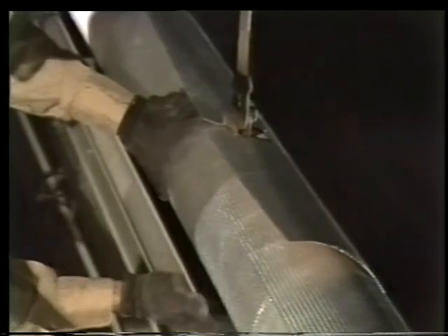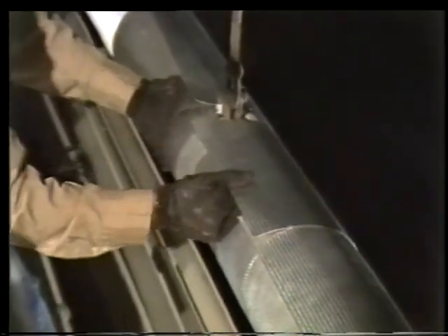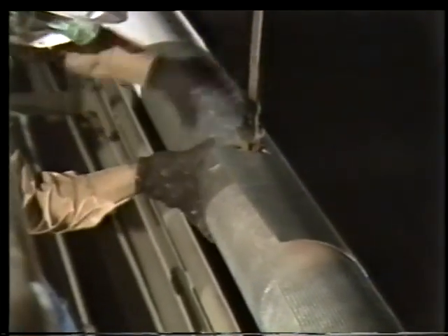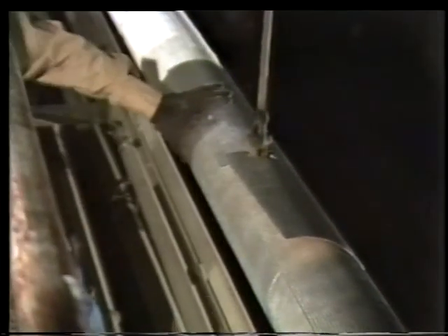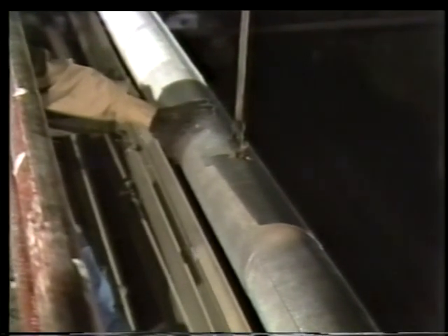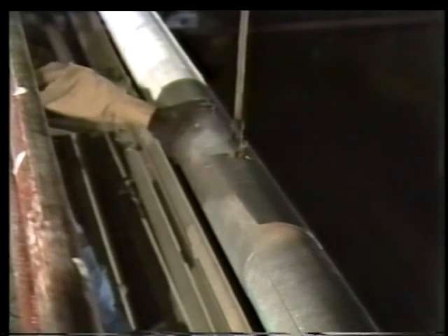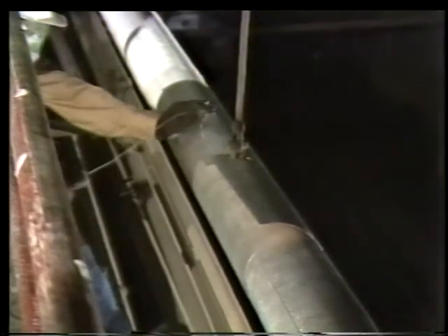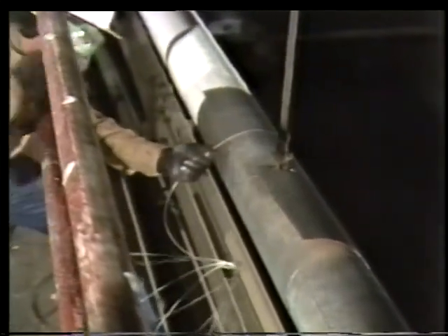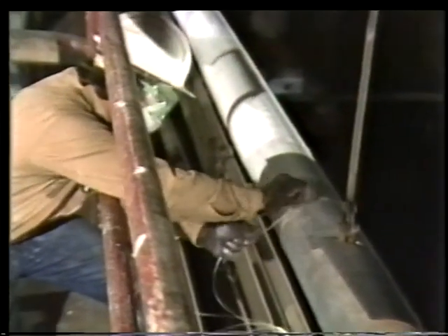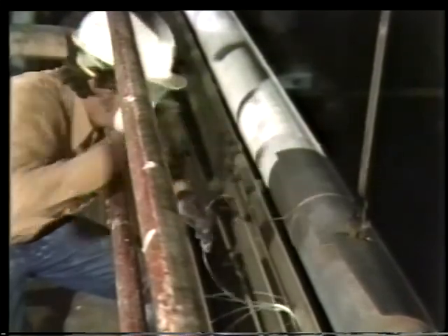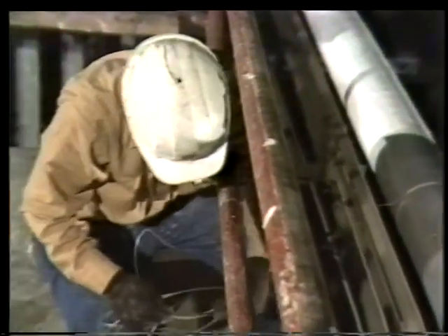Each jacket overlaps the other by 3 inches, about 7.5 centimeters. One edge tucks under the neighboring jacket, and the other edge wraps around the outside. This helps lock the jackets together while providing for expansion space between the joints. This is important because as the pipe heats up, the metal expands, causing the pipe to become longer. This tends to spread the joints apart, leaving gaps between the sections of insulation. The overlapping jackets cover the gaps and help prevent heat losses between joints.